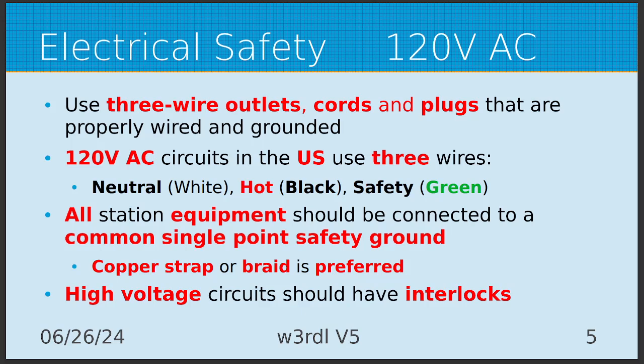All station equipment should be connected to a common single point safety ground. Copper strap or braid is preferred. Strap is probably your best bet outdoors, and if you can't use strap, use a heavy gauge single conductor wire for your ground. Braid isn't great outdoors because stuff gets into it and causes corrosion. High voltage circuits should have interlocks.